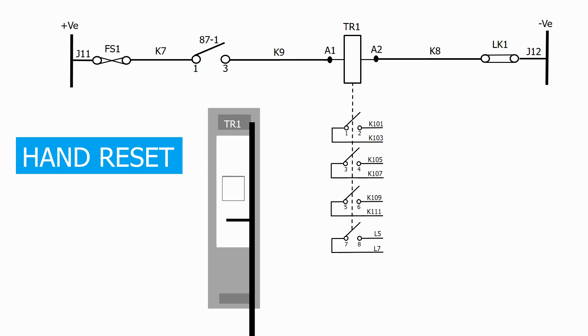Again, the flag and contacts operate when the relay is energized, but the contacts and flag don't change state when the initiation is removed and the relay coil de-energizes. To reset the contacts and the flag, we need to physically push the lever on the relay up.